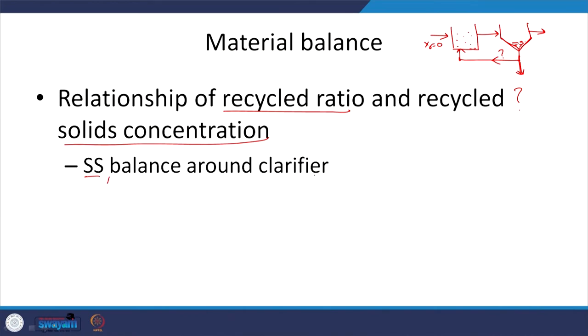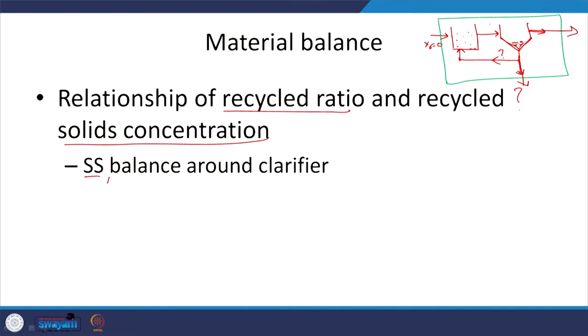If the sludge is not settling well — meaning the suspended microbes are not settling — I have to increase the recycle flow, otherwise the plant operation is going to be affected. So here we are going to look at a steady-state balance around the clarifier. Until now we looked at the mass balance around the entire system, but to understand the recycle ratio we need to apply the mass balance around just the clarifier, so that the recycle flow is captured in the analysis.